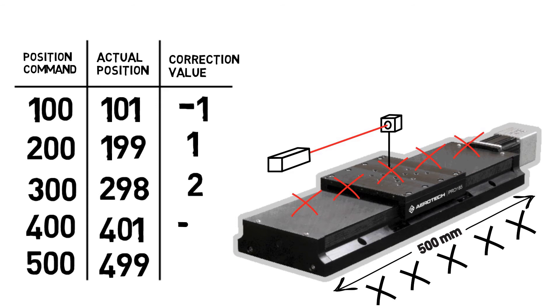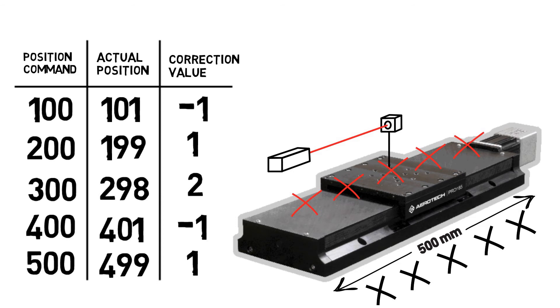The end result is a lookup table that can be used to correct the position of the stage throughout the travel range, improving accuracy. Any sufficiently advanced motion controller can incorporate this lookup table and use it during all motion commands so that the stage moves to the correct position without the laser interferometer.